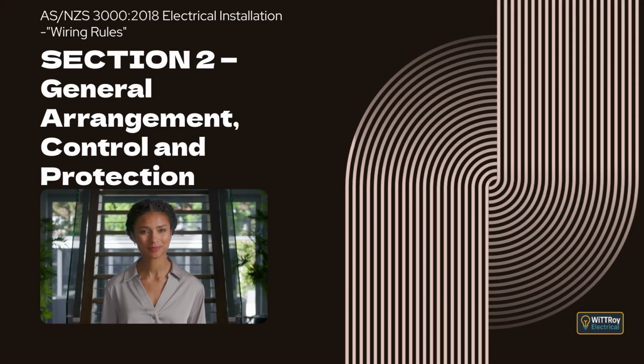Clause 2.3.5.2 Emergency switching devices. An emergency switching device must be able to remove the hazard quickly. It may be a single device that interrupts the incoming supply, or a combination of devices that act together by a single action. The device must be able to break the full load current of the equipment, including stalled motor current where needed. If the device is manually operated, it must interrupt the main circuit directly.